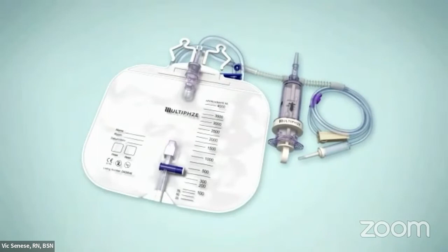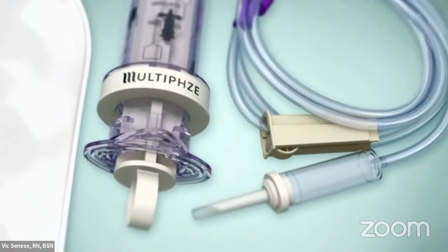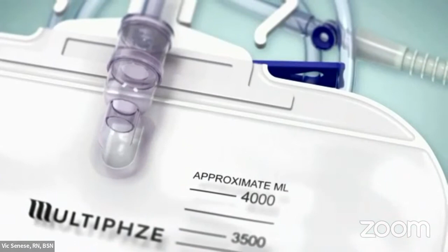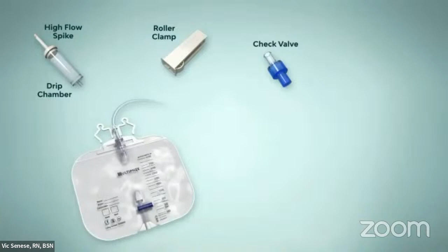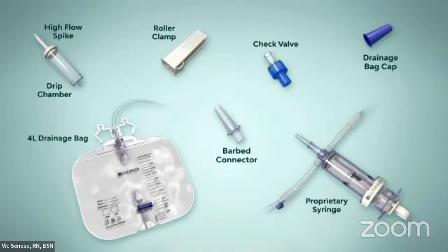The Multiphze enclosed bladder irrigation system is an OSHA-compliant novel solution for irrigating the bladder when treating hematuria. It is designed to reduce the risks and costs associated with biohazard exposure, while delivering improved procedural efficiencies from manual bladder irrigation procedures. The Multiphze system has a high flow spike, drip chamber, roller clamp, check valve, drainage bag cap, barbed connector, and proprietary syringe. Barbed connectors attach the Multiphze irrigation line and drainage bag to the custom syringe. Each can be disconnected to transfer the irrigation line and drainage bag to the patient's 3-way catheter for continued use as needed.